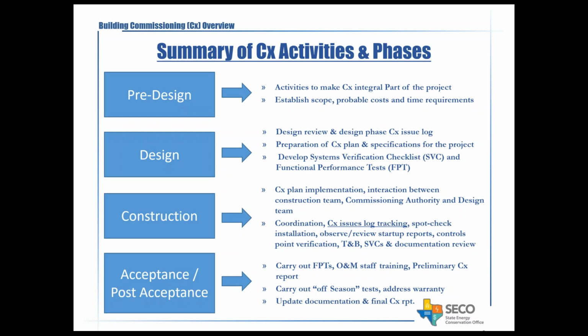There's good coordination, and most importantly, during the construction phase a commissioning issue log will be developed for tracking issues identified by the commissioning agent. There will be spot checks, review of reports, control point verifications, test and balance contractor report reviews, and primarily documentation, making sure any identified issues are being addressed. The commissioning issue log is maintained by the commissioning agent, who is also involved in distributing and collecting that information, making sure any open items are closed and addressed.